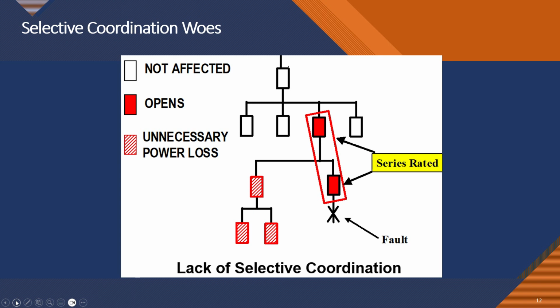Inherently, series rated systems are not selectively coordinated. They can't be. A line side protective device has to open to protect the load side of the circuit breaker. So I cannot have a larger breaker ahead do all the heavy lifting to cover my short circuit current rating. I cannot have series rating with selective coordination. Let's just leave it at that.